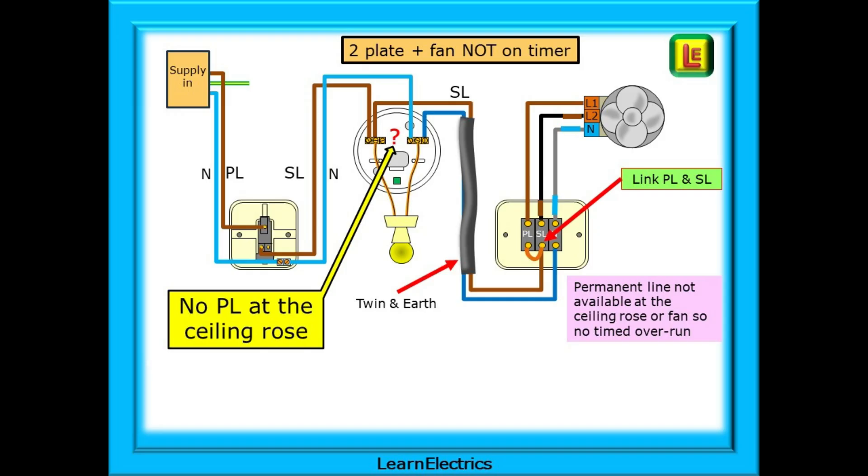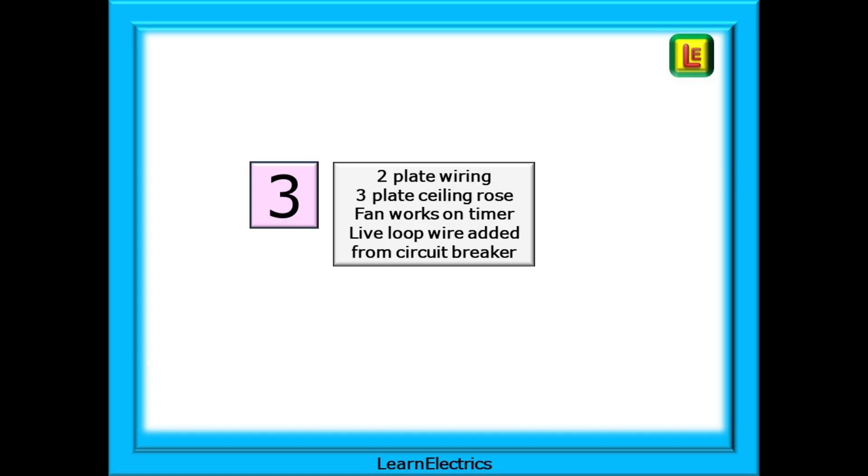There is no permanent line or PL at the ceiling rose. You may come across this with older installations where two plate wiring has been used and now it's difficult to run a permanent line to the newly installed fan. In this case there is only the switched line and neutral available for the fan plus earth of course. To make the fan work we must link the switched line terminal to the permanent line terminal at the isolator switch or link L1 and L2 at the fan. The fan will only operate when the light is turned on. If the circuit had a three plate ceiling rose and we could run a permanent line to it then we could enable overrun of the fan.